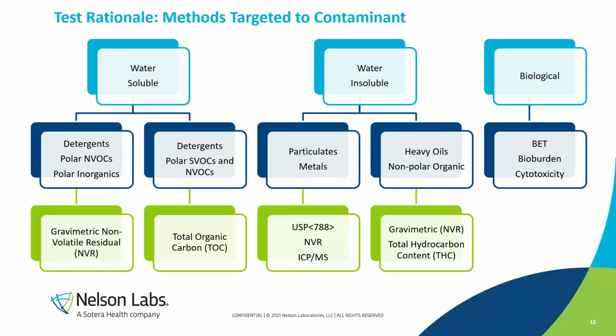Versus total organic carbon, TOC. This is another water extraction. It is not specific to non-volatiles. So if there's IPA maybe in a blind hole of your device or a textured area that just kind of got stuck behind, TOC would detect that as a little more volatile. But it is specific to organics. If you have inorganics on your device, TOC is not going to catch that. You'd have to go back to gravimetric or another method.